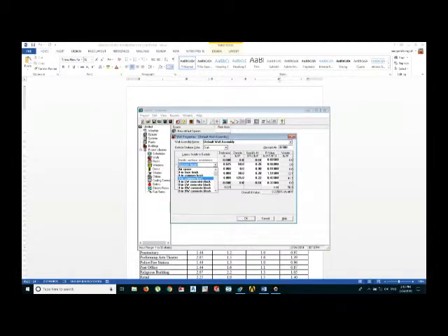Like my wall is made up of 8-inch common brick. There is no airspace. There's insulation of R14 board insulation. Third one is stucco, which is a 1-inch plaster, and there is a wood siding. So my wall is made up of all these materials. You can define your own wall material here, or you can put it manually. Its R value, its density section. Just press OK.